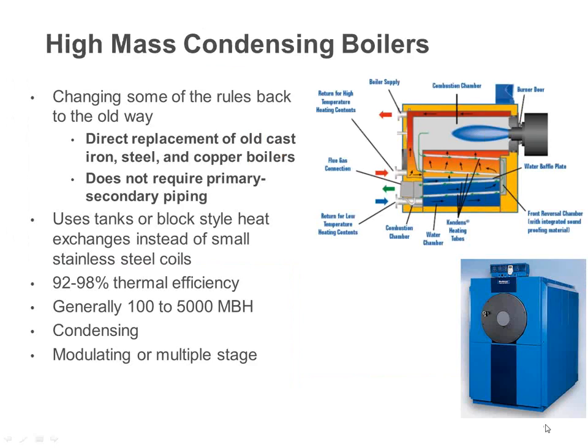If you look at the way the flue is going through here, the coldest water is at the very end of the system. So basically it is condensing the most right there and keeping the whole unit's efficiency very high. And since it is such high mass, we don't have a pressure drop in the boiler, and a lot of these don't even require a dedicated boiler pump. So it's something to look at when you're dealing with the larger boilers, schools, that kind of stuff.